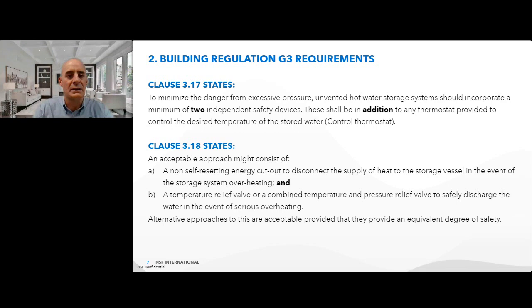Clause 3.18 states that an acceptable approach might consist of 1, a non-self-resetting energy cutout to disconnect the supply of heat to the storage vessel in the event of the storage system overheating, and 2, a temperature relief valve or combined temperature and pressure relief valve to safely discharge the water in the event of serious overheating. Alternative approaches to this are acceptable, provided they give an equivalent degree of safety.